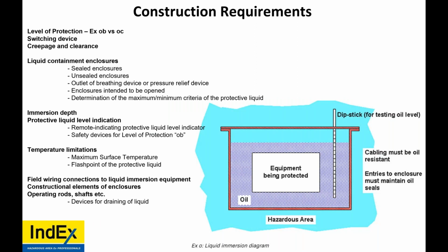So, construction requirements for Ex o. What do we have? Well, we have an equipment being protected, surrounded by oil. It will have a dipstick or a level indication, and the hazardous area will be outside. So via exclusion, it excludes the hazardous atmosphere from getting close to the piece of equipment that could cause a potential source of ignition. So what construction requirements do we need to look at? Well, level of protection, switching devices, creepage and clearance, liquid containment enclosures, immersion depth, protective liquid level indication, temperature limitations, wiring methods, constructional elements of enclosures, and operating rods and shafts.